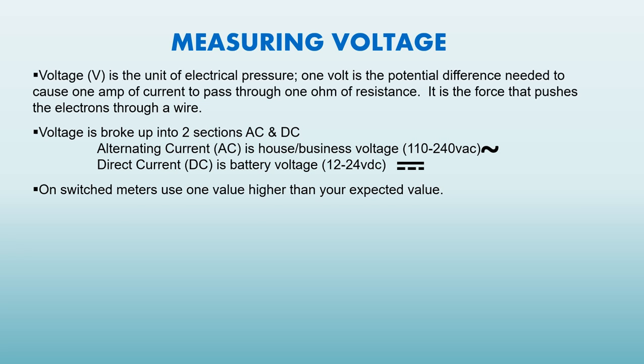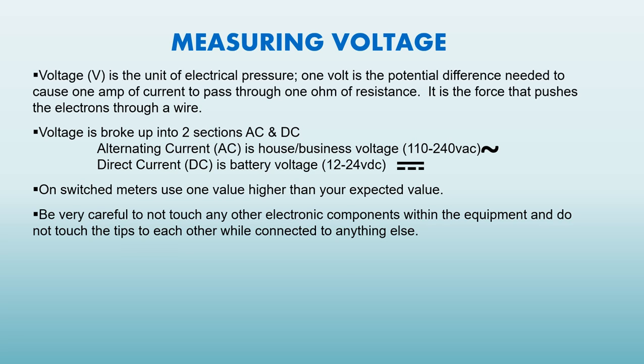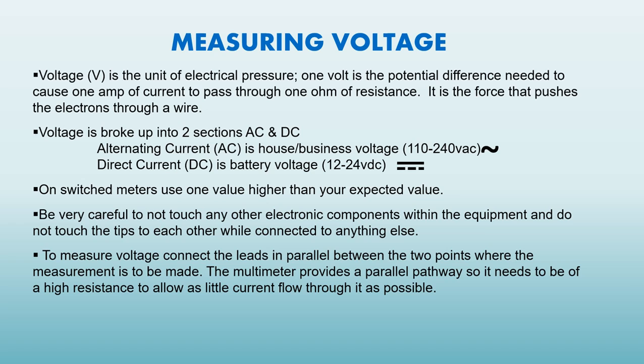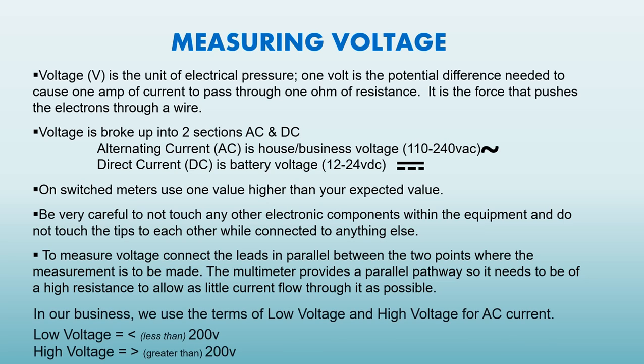On switched meters, use one value higher than expected value. Be careful not to touch any electric components within the equipment and do not touch the tips to each other while connected to anything else. To measure voltage, connect the leads in parallel between 2 points where the measurement is to be made. The multimeter provides a parallel pathway so that it needs to be of a high resistance to allow as little current flow through it as possible.